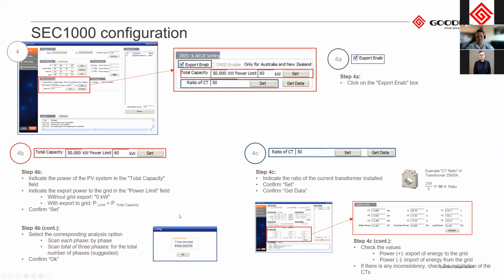So especially if you have net metering or anything like that, scan total of 3 phases is most likely going to be the best to use on a commercial site. But please make sure that it is within your regulations. If you're not allowed to export at all, make sure you say scan each phase. But if it's net metering and they don't mind some export on one phase while usage on a different phase, just a general balancing, then you can use scan total.